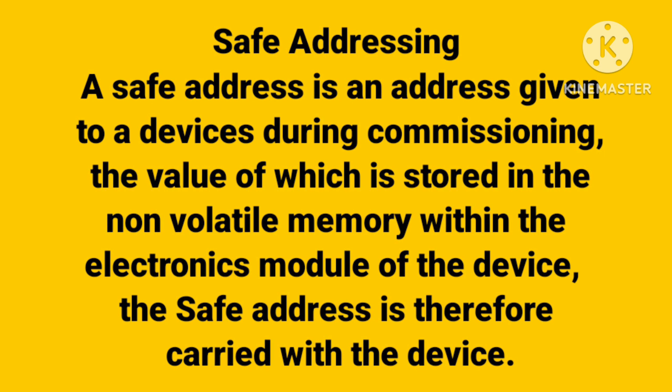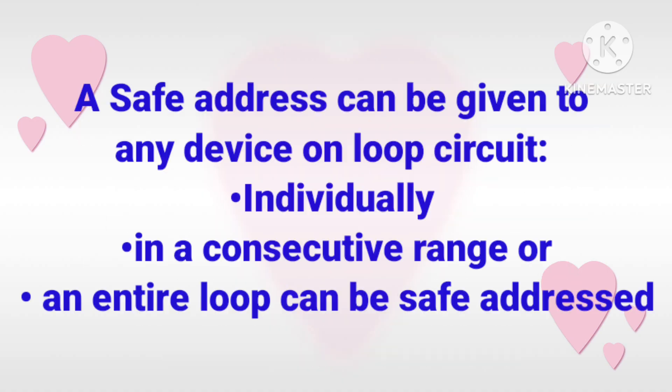So if we replace the device, the panel will note the serial number change, and because of that the label of the panel will remain the same — even if we remove any device from the loop, the label stays the same because we have safe addresses. Any new device added will be assigned to the last address, after the last address.